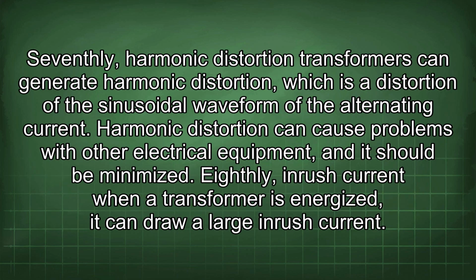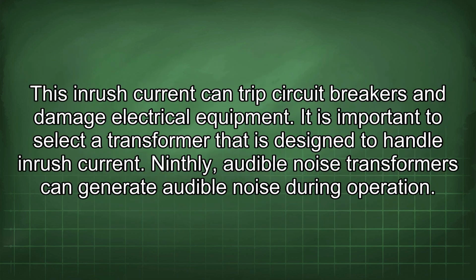Seventhly, harmonic distortion. Transformers can generate harmonic distortion, which is a distortion of the sinusoidal waveform of the alternating current. Harmonic distortion can cause problems with other electrical equipment, and it should be minimized. Eighthly, inrush current. When a transformer is energized, it can draw a large inrush current. This inrush current can trip circuit breakers and damage electrical equipment. It is important to select a transformer that is designed to handle inrush current.